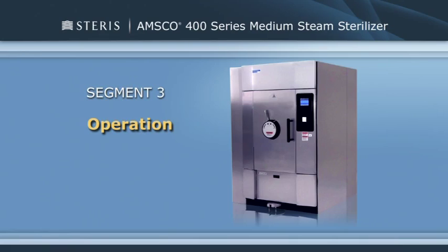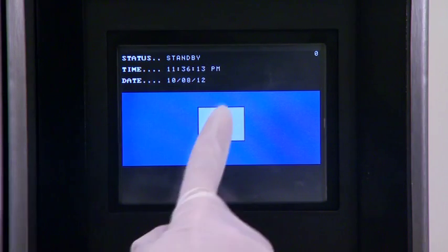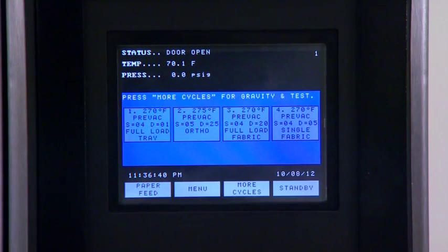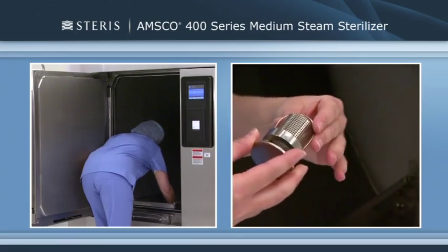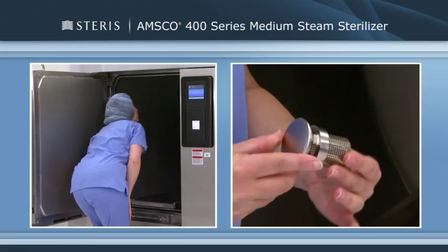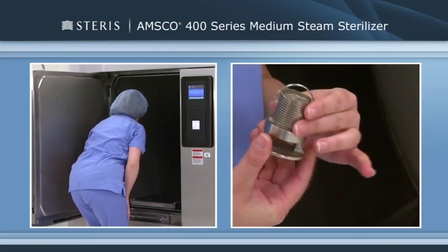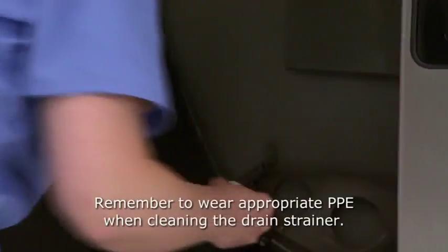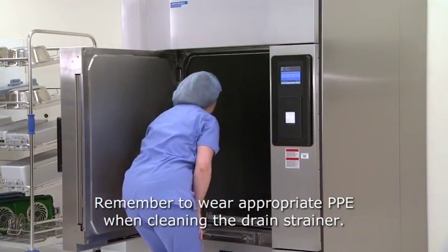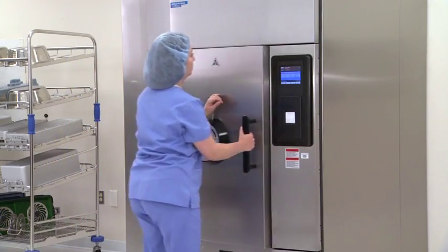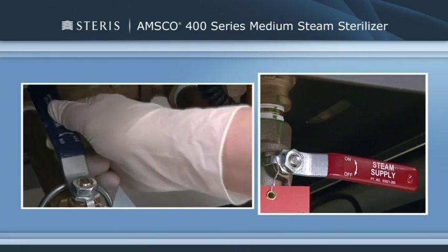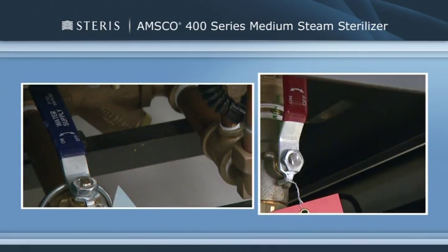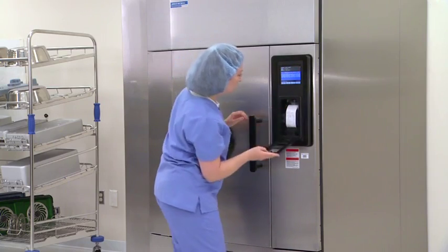Now that you've been oriented to the unit and its basic design and function, let's cover how to operate it and run a cycle. Press the On touchscreen button on the control display. STERIS recommends inspecting the interior chamber and chamber drain strainer each morning before running the daily warm-up cycle. Open the chamber door and check that the drain strainer is clean and in place, and that the chamber interior is clean. Close the chamber door. Verify that the utility supply valves are in the open position. Open the control access door.